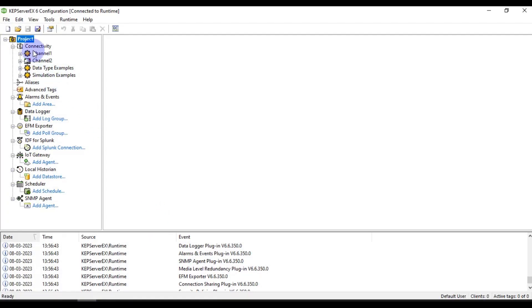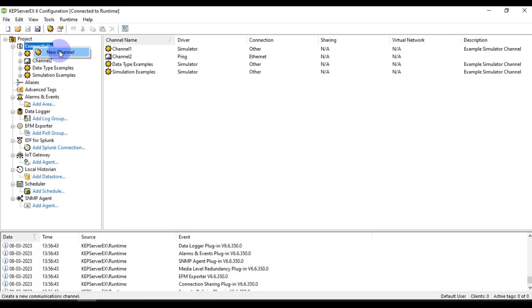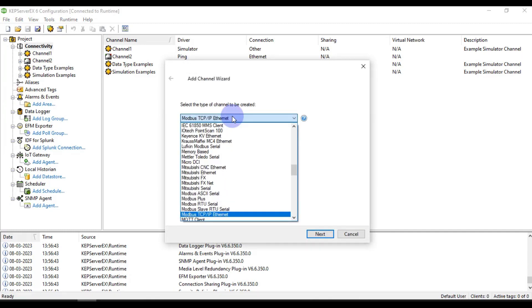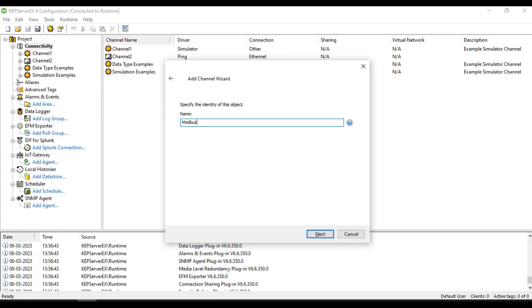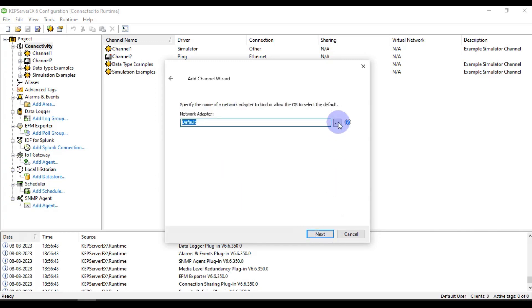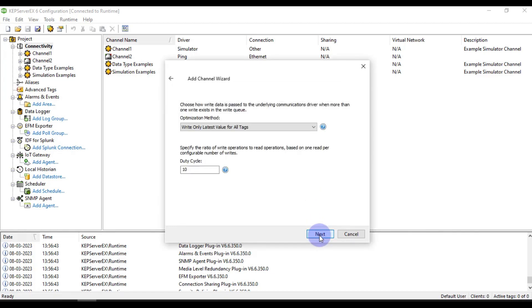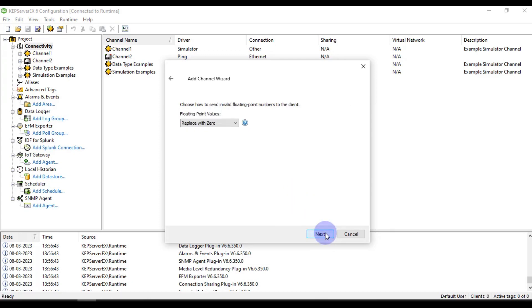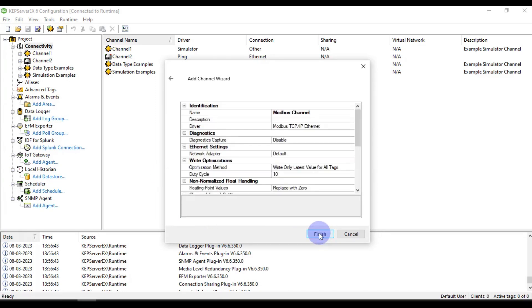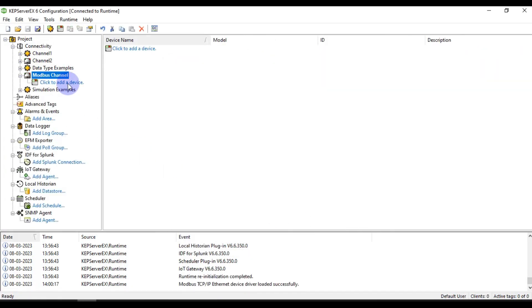First of all we will go to KEPServer and create a new channel. Go to Connectivity and press on New Channel. It will be our Modbus TCP/IP Ethernet channel. Press Next, name it as Modbus Channel, then press Next again. The network adapter will be default. Press Next through the remaining steps. The port number will be 502, protocol TCP/IP.